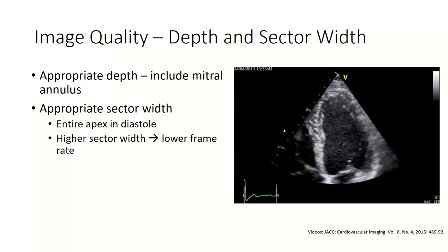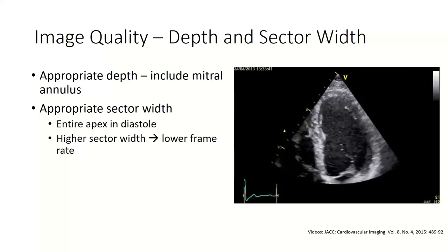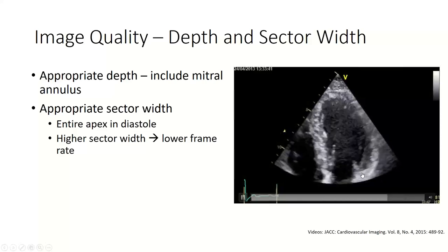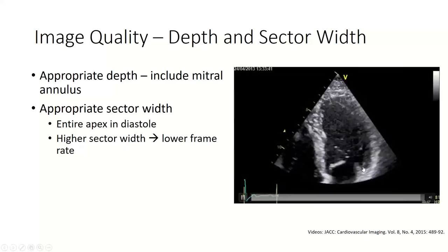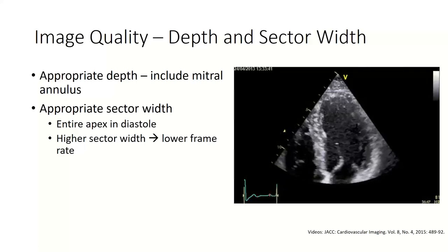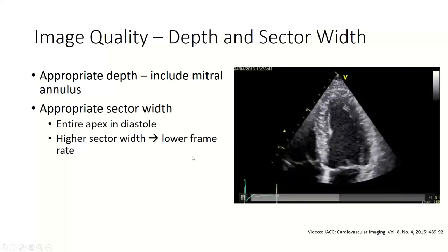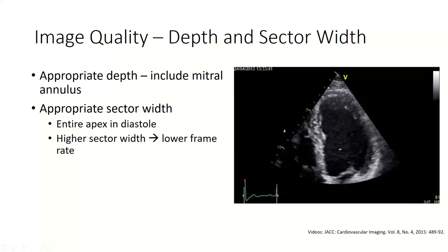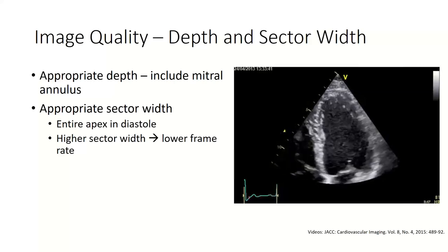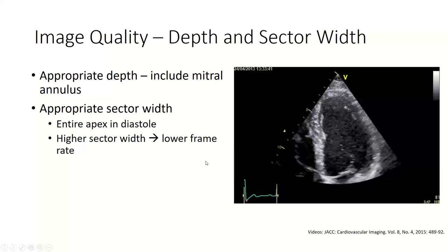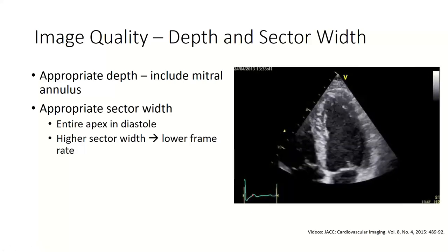Depth and sector width are important because of our need to establish a region of interest. Recall that region of interest is the green line around the compacted, non-compacted myocardium. We need enough depth to see the mitral annulus, and we need to see the entire apex in diastole to allow for appropriate tracking. However, increasing depth and sector width will drop our frame rate and influence tracking.